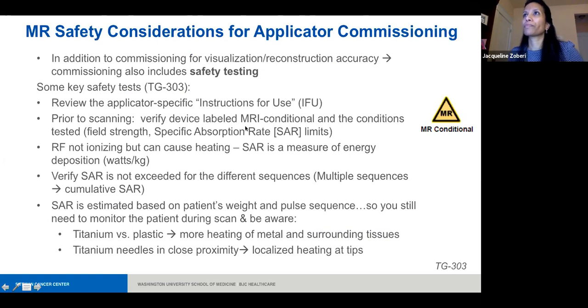When commissioning these applicators for visualization and reconstruction accuracy, it's really important to also consider safety tests. This is well addressed in Task Group 303, or will be. The first recommendation is to check the instructions for use, the IFU, and make sure prior to scanning or even purchasing equipment that you verify the device is labeled MRI conditional.